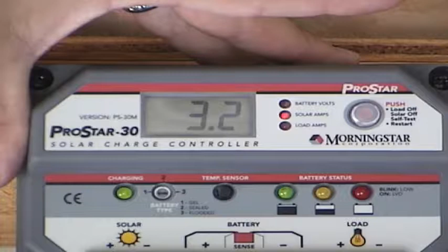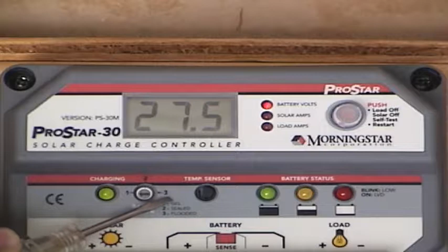Now select the proper charging for the batteries being used. Turn the rotary switch with a small flathead screwdriver to the battery type printed on the label. If you purchase the flooded batteries that I listed on the system parts list, then you will need to turn the rotary switch to number 3.